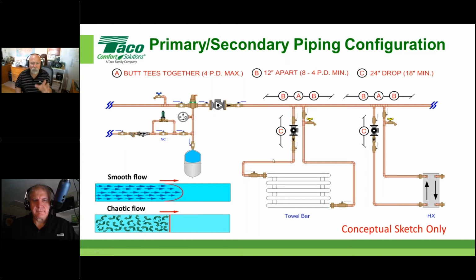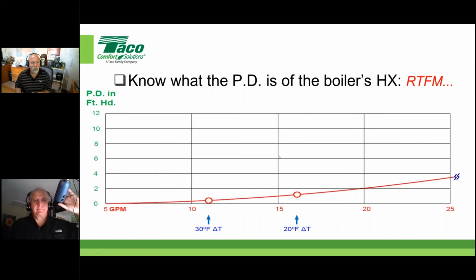So anyway, I hope that helps, and I'm sure there might be some questions out there, but for the sake of time, let's jump into the boiler's heat exchanger. I've put a big note here: know what the pressure drop is of the boiler manufacturer's heat exchanger, and you guys can wink and nod if you know what that means. This is just generic, it doesn't apply to anybody specifically, but what we're showing you is go to the boiler manufacturer and look at a given gallons per minute flowing through that exchanger. What is the resultant pressure drop?